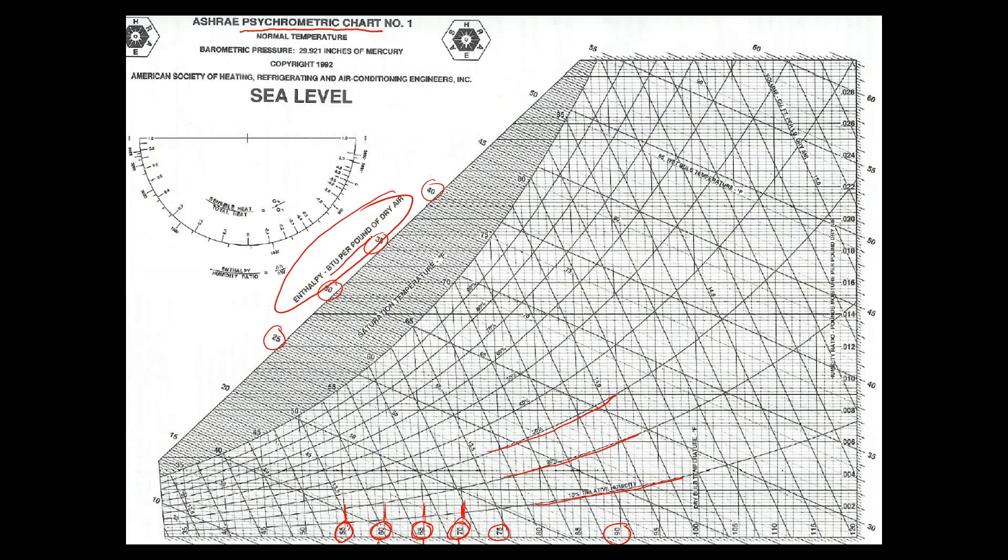Let's do an example here. Let's say we had 90 degrees and 55% relative humidity. So I would start down here at 90 degrees. If I was given conditions like that's the temperature outside, and it's 55% relative humidity, I would be somewhere right about where this dot that I'm circling right now. Because you can see the 90 degrees, you would go up, and I said 55% relative humidity. You can see this is 50, this is 60. Right about here would be about 55% relative humidity.